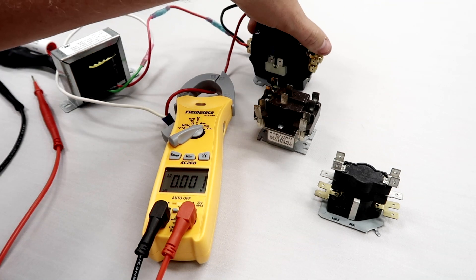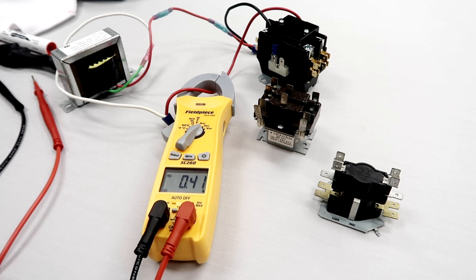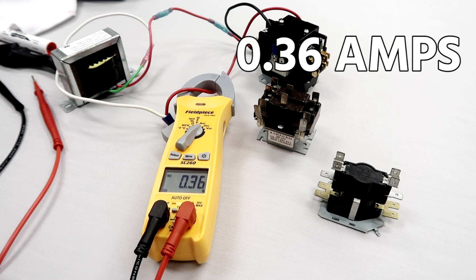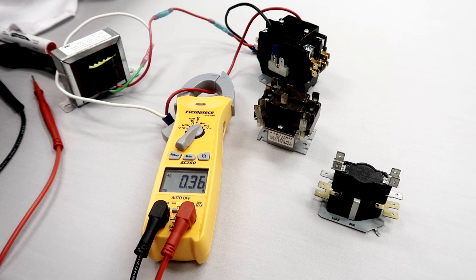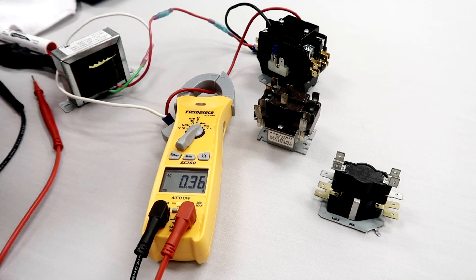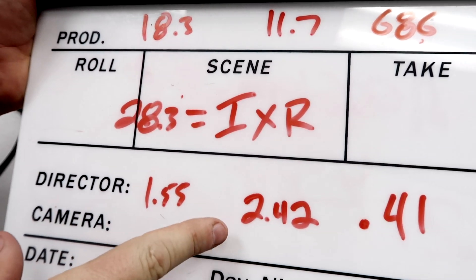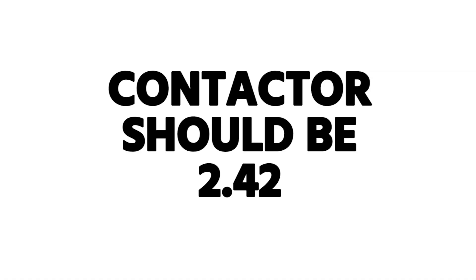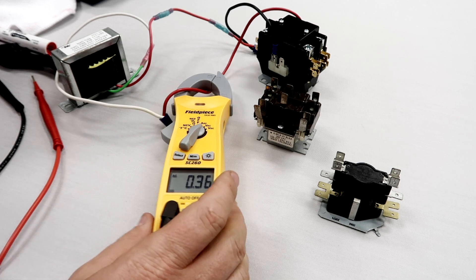This is the electromagnetic coil that I'm plugging into on both sides to a 24-volt transformer. I'm going to flip the switch on. You heard the contactor pull in, and our amps are only 0.36 amps. We had calculated 2.42 amps, but in actuality we only have 0.36, which means Ohm's Law is not a liar — we have some resistance showing up somewhere, and that resistance is what we call inductive reactance.